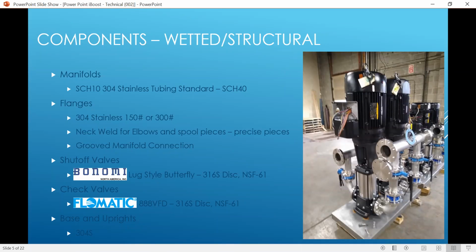We do use stainless steel. We don't use copper on our headers. Our headers are rated at either your 150 pound or your 300 pound, depending on the pressure in the system. We use neck welds for elbows and spool pieces, and it's pretty good construction, as you can see by the picture there. That's pretty much an average system that you'll see that comes out of our shop there on the picture. As far as shutoff valves, we use the Bonomi lug style, which has your 316 disc and it's NSF 61372. Your check valves are your Flomatic.